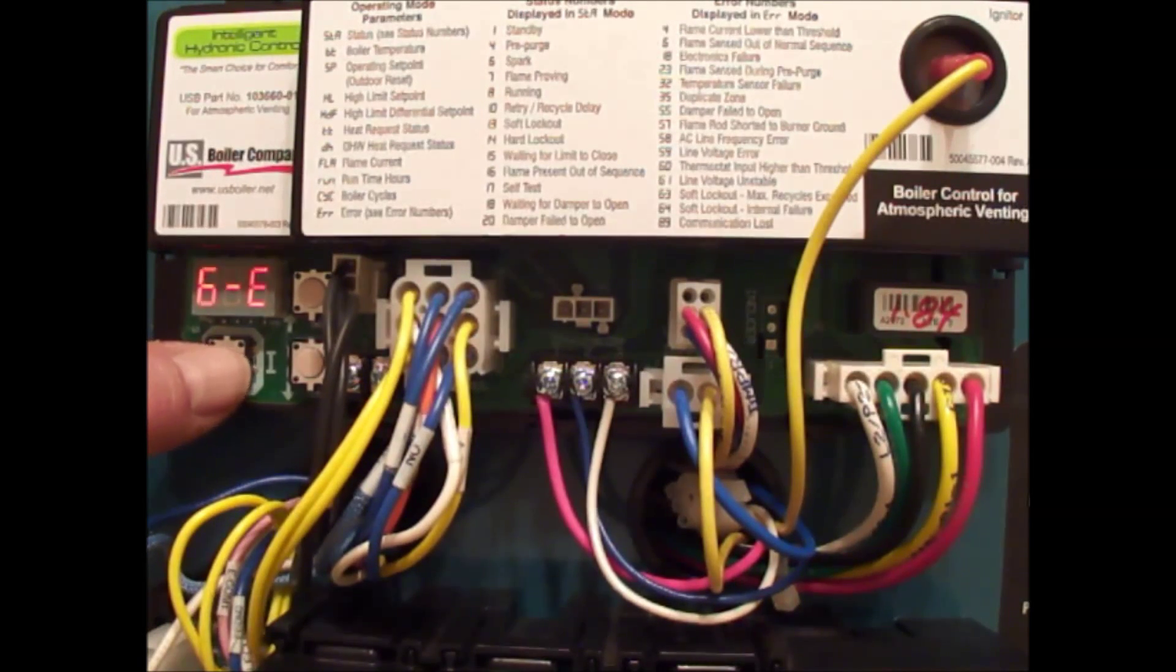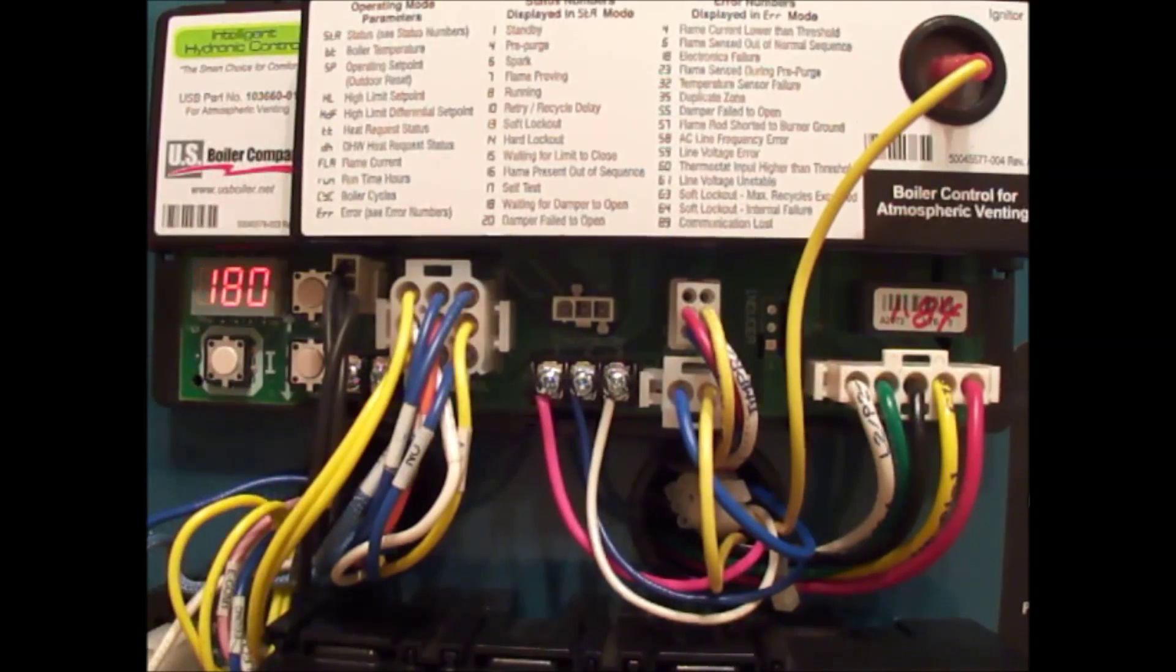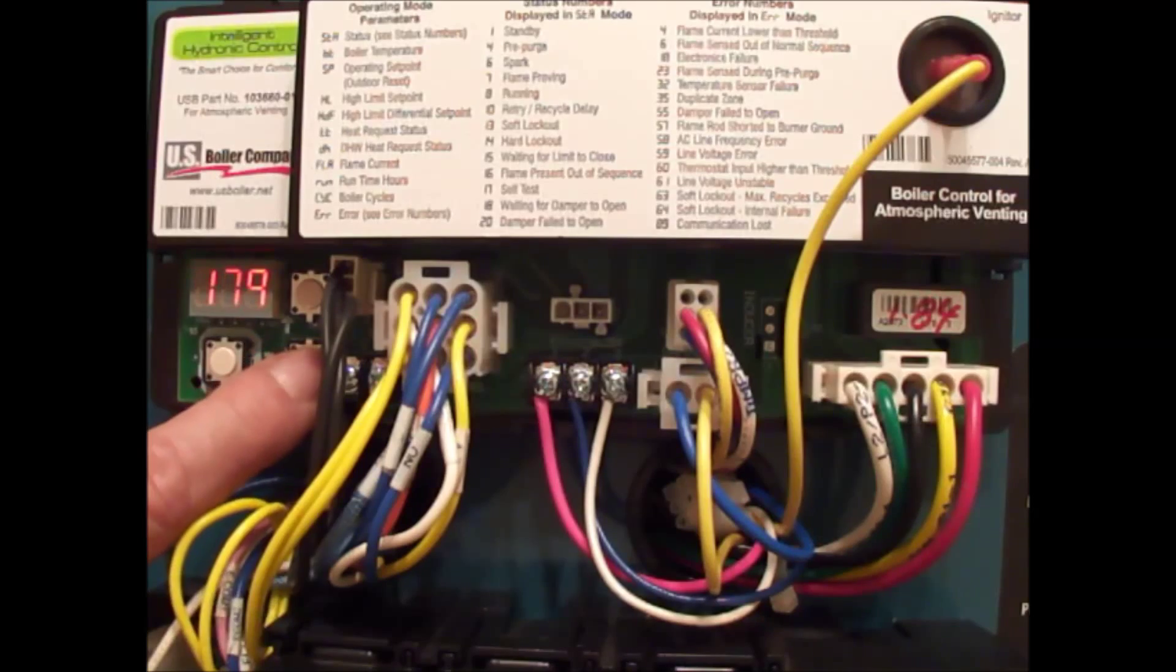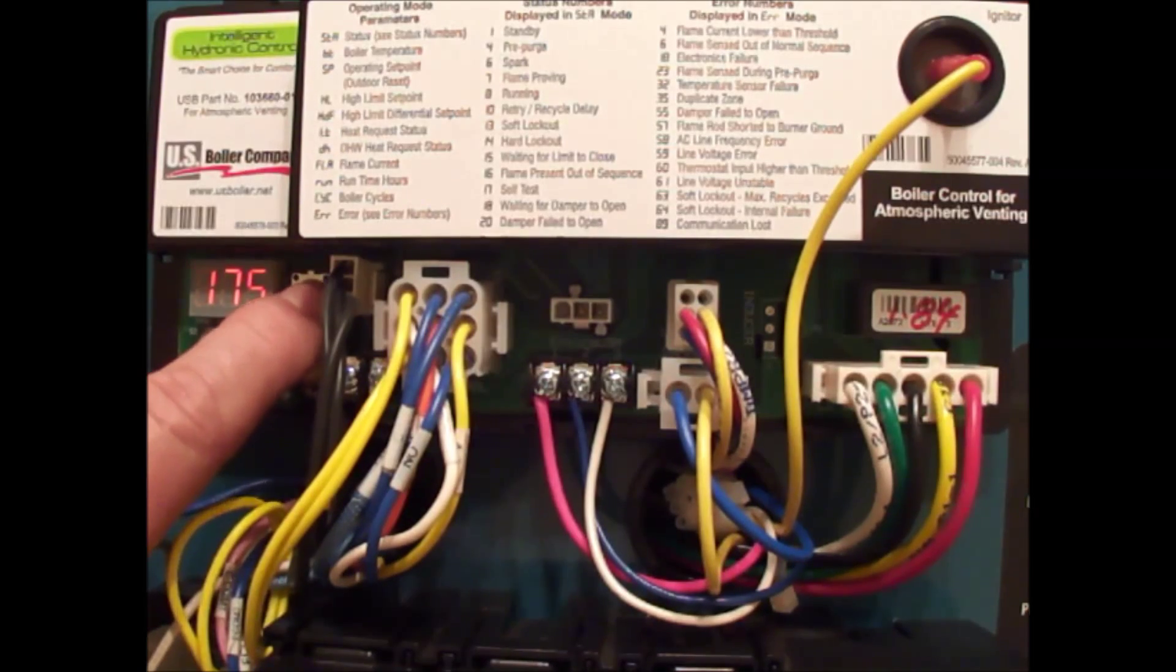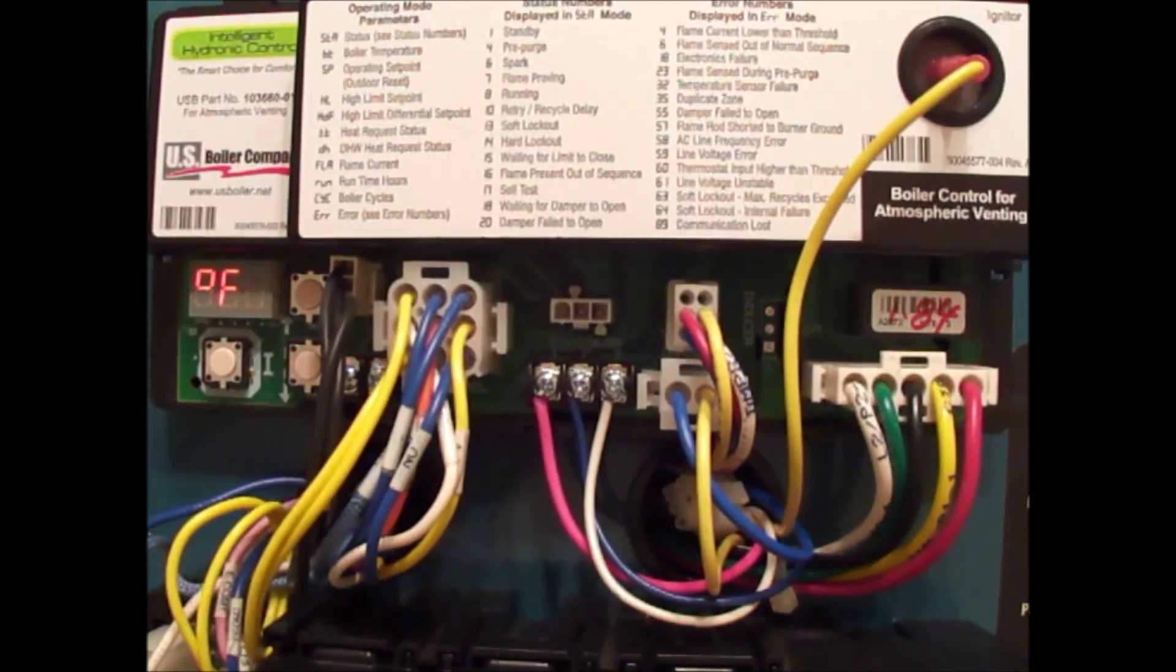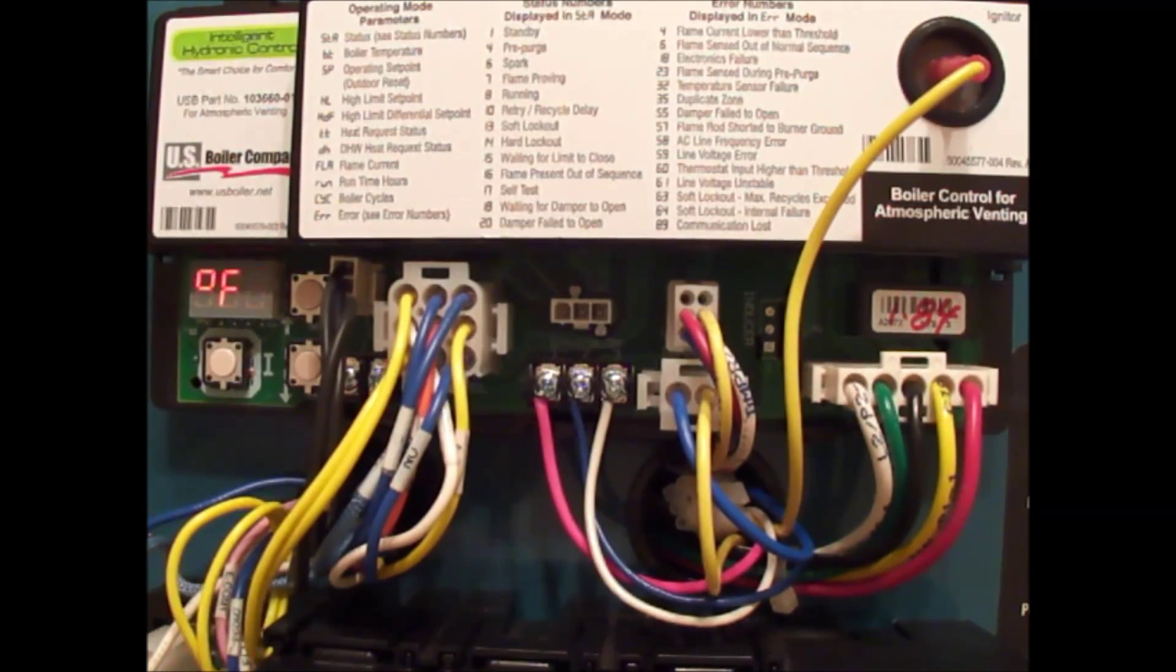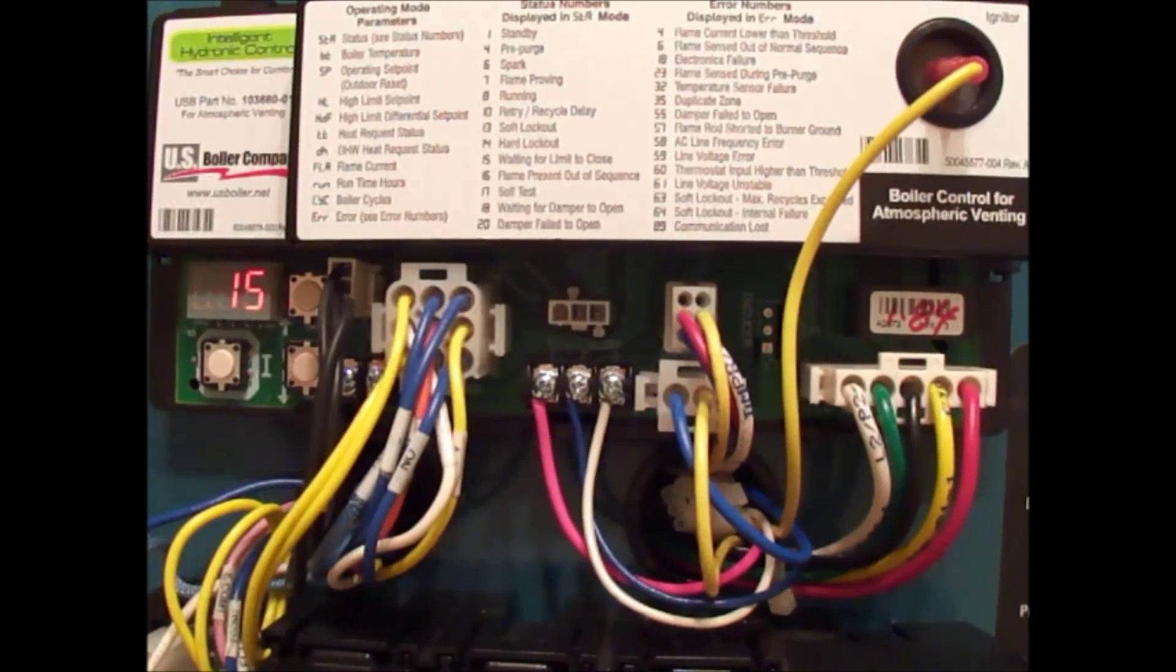Let me go around to the beginning. The first one we look at is high limit. We can change the high limit up or down; it is defaulted to 180. If we make a change, as soon as we hit the i button it saves automatically. Next one's differential—we have a 15 degree differential on this control.